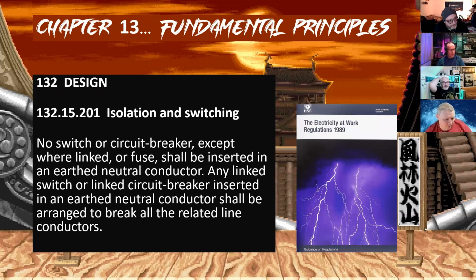Carrying on, regulation 132.15.201, a UK specific reg. For those who may not know, if it ends in 201, it's UK specific. No switch or circuit breaker, except where linked, or fuse, shall be inserted in an earthed neutral conductor. Any linked switch or linked circuit breaker inserted in an earthed neutral conductor shall be arranged to break all the related line conductors.